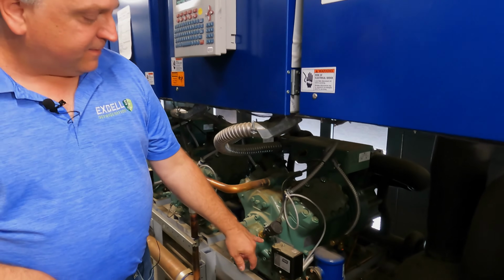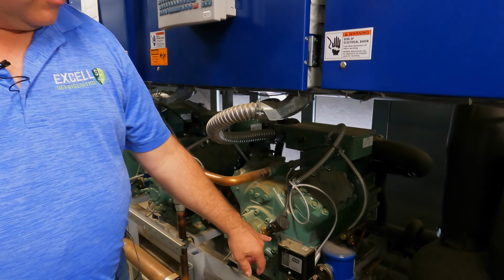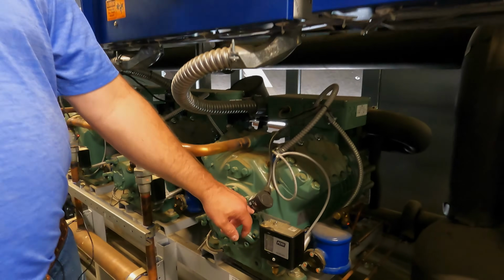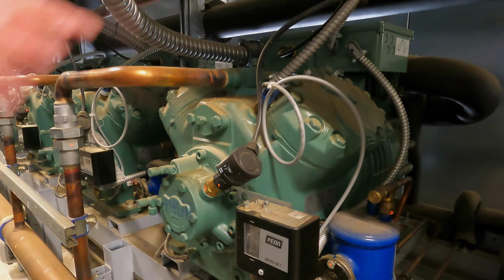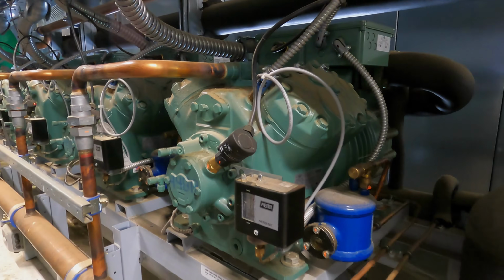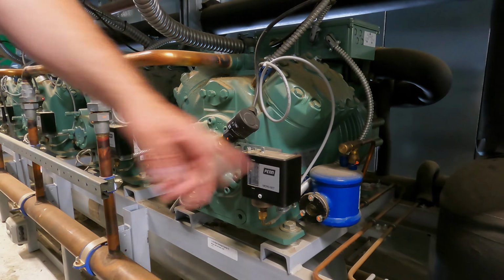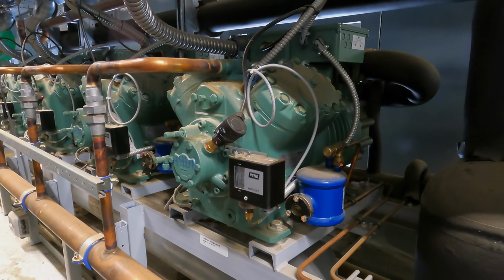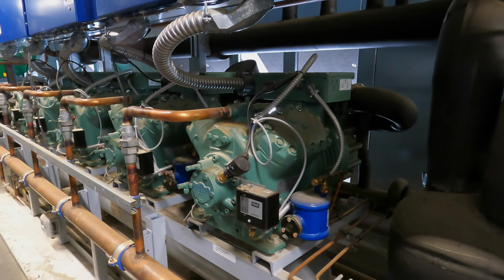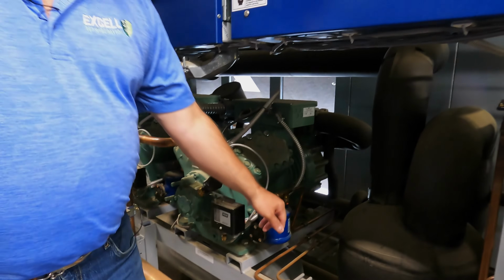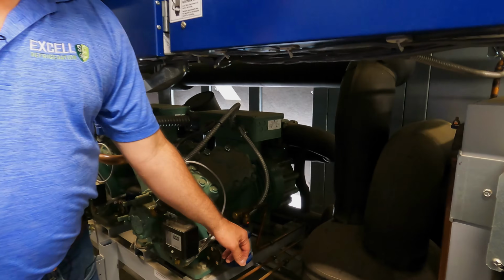We also have our sensor for oil, so it's sensing oil pressure. And if we lose oil pressure, we're going to turn the compressor off because we want to save it. We also have a low pressure switch. If we get too low of a pressure, we don't want to pull in a vacuum, so we're going to shut the compressor off.